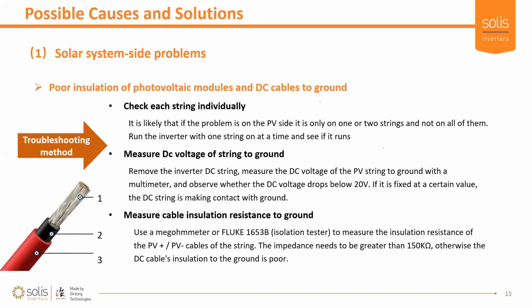If you're getting this alarm on this inverter, I would suggest trying each string individually. It is unlikely that all the strings have the same problem. It would be quite strange unless it's been left like that for a long period of time. So that's a very nice, quick, easy test to perform.